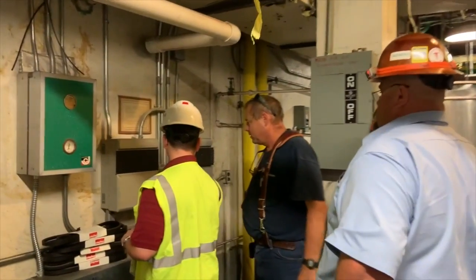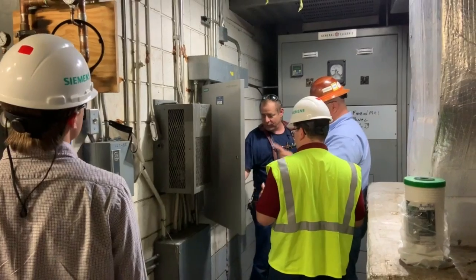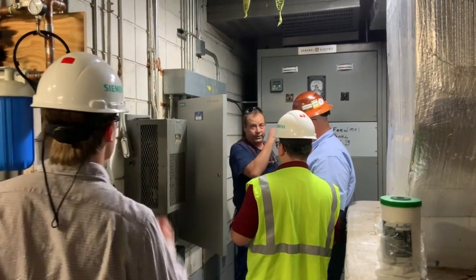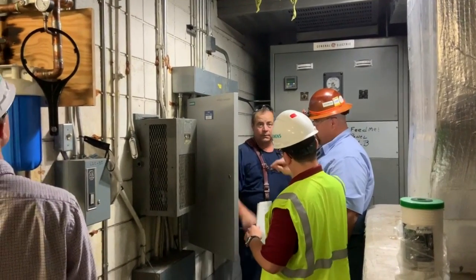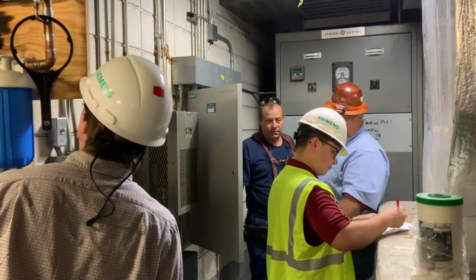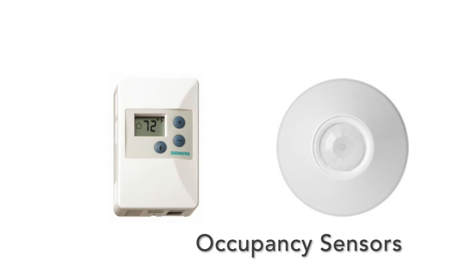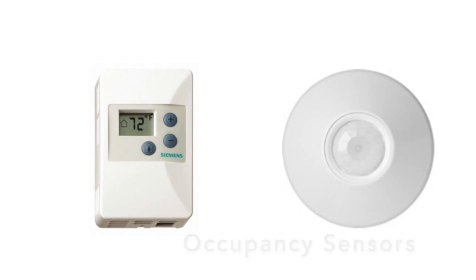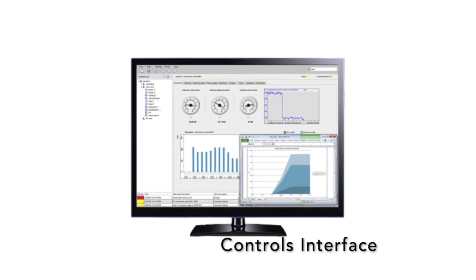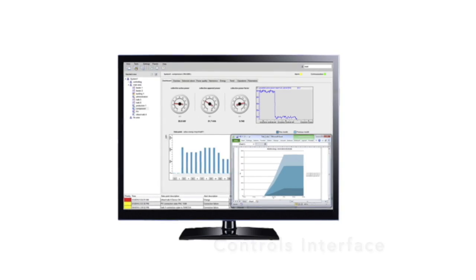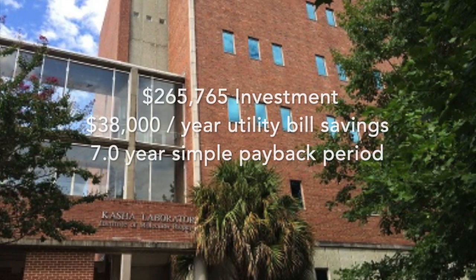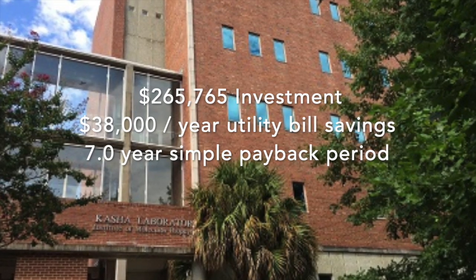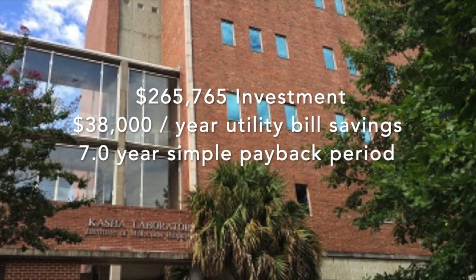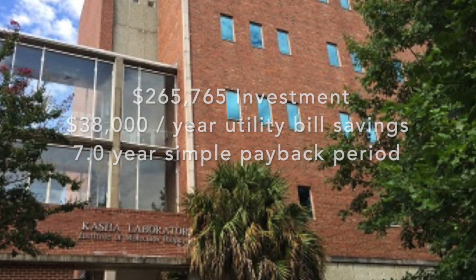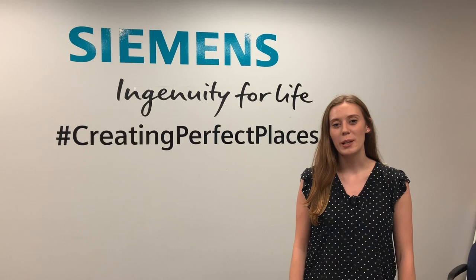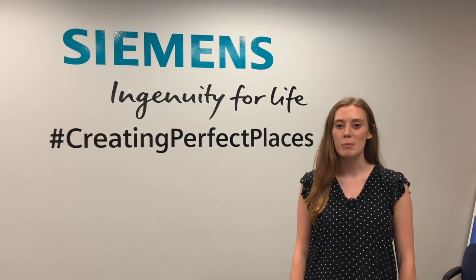The metrics observed were the air handling units' supply and return air temperatures, pumping performance, water flows, and flow meter accuracy. In addition to identifying operating issues, Siemens recommended four energy conservation measures: installing occupancy sensors, adjusting the demand control ventilation, building schedule and set points, and adding energy monitoring equipment and software. The upfront investment in this project was $265,000. The savings will result from an annual utility bill reduction of $38,000, and the project will pay for itself in seven years. So through this project in my internship at Siemens, I've learned a lot about building performance services and reducing energy consumption on a large scale.